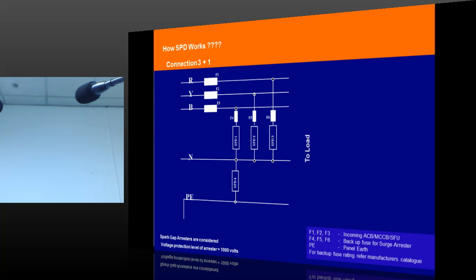SPDs are nothing but maybe a spark gap or a varistor or a diode. These are voltage operated devices. It means, you imagine that this one, SPD4, is a spark gap. Spark gap means a spark over in a gap. There are maybe 2 plates and air in between. Once the potential difference between the terminals of the SPD crosses certain limits, then there is a flashover. You imagine that the voltage protection level is, let's say, 1 kV. High potential is created in the earth line because of lightning strike. High potential.